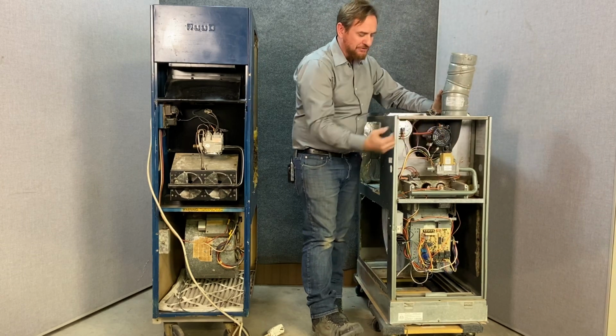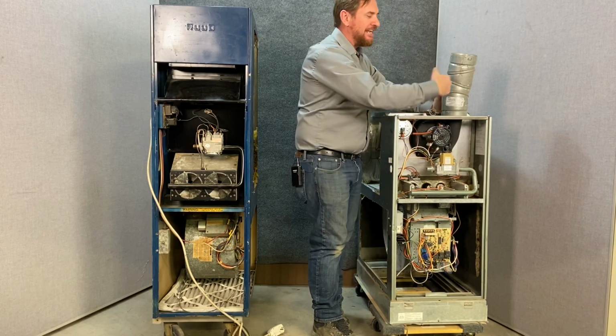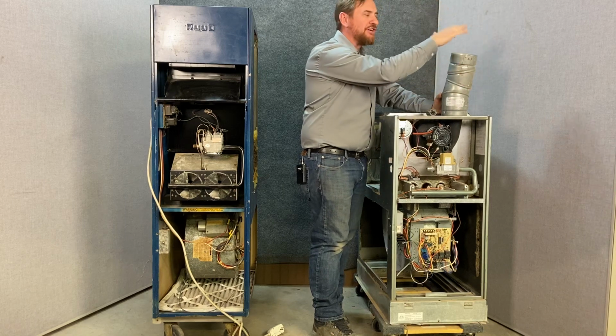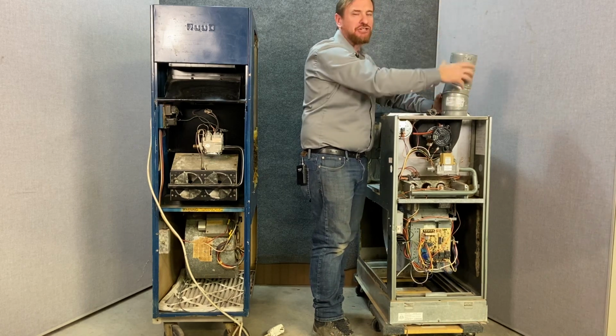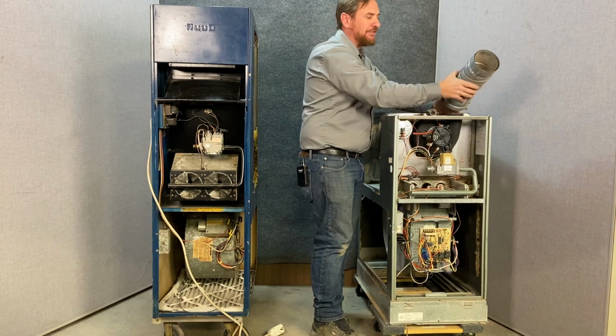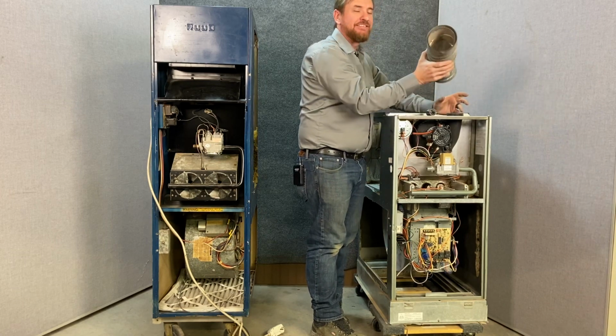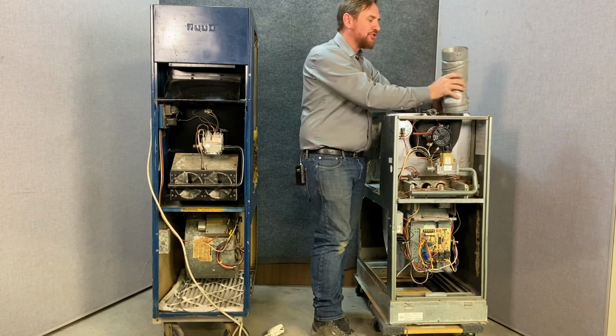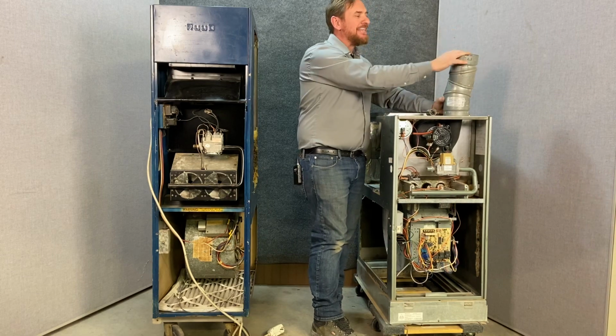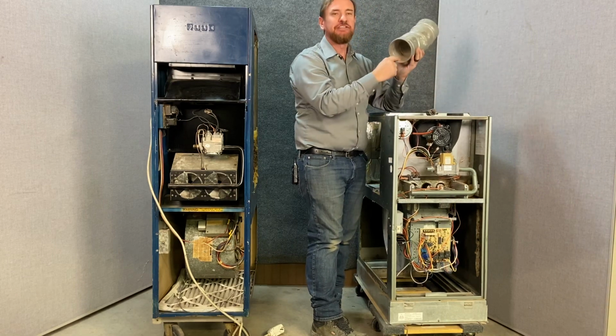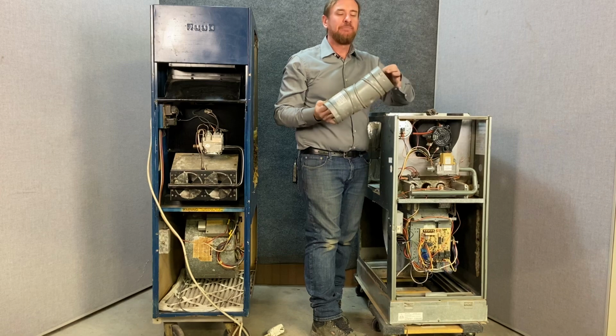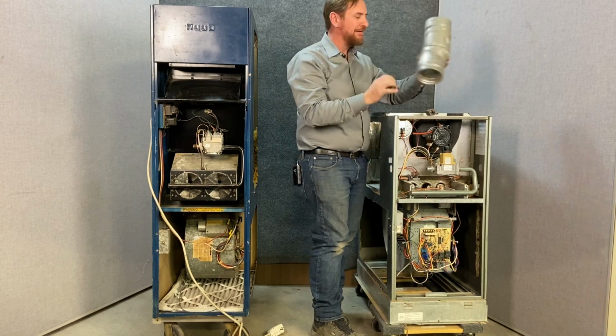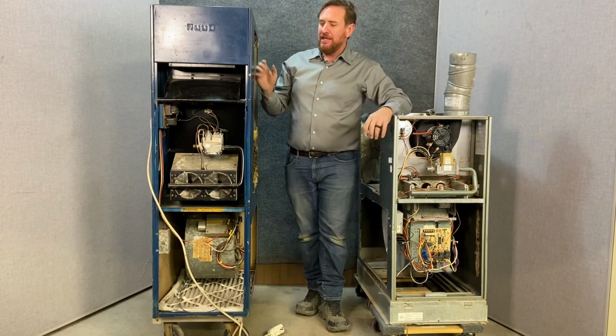This fan motor's job is to pull a draft through the heat exchanger and induce or start a draft, but its job is not pushing. It's not pressurized on the side. I've seen people want to put the flue pipe going horizontally because they think that it's pushing air, and that's not true. So you need to keep that in mind. Anytime you're changing any furnace, you always want to check the flue pipe to make sure there's no cracks, make sure that there's no corrosion or water damage inside of that flue pipe.